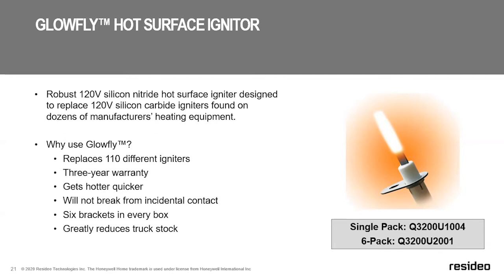Comes in a single pack, which is the part number you see there, the Q3200U1004. But the cool thing, and the way I like to promote this product, is with the 6-pack. One, because the day that you have only one in the truck, you're going to need 2. But the cool thing about the 6-pack is on the back side of the box is a diagram that shows the most common OEM igniters out on the market. Then you just take the broken igniter you're pulling out and match it up to the box, and it tells you which set of brackets to use for that particular installation. It's a fantastic thing, and it's a really durable igniter that lasts a long, long time.